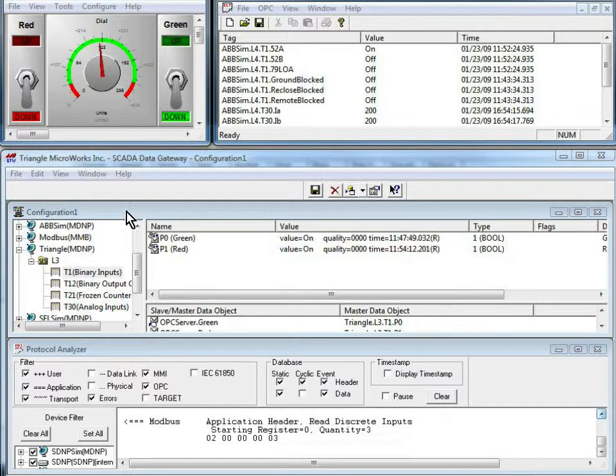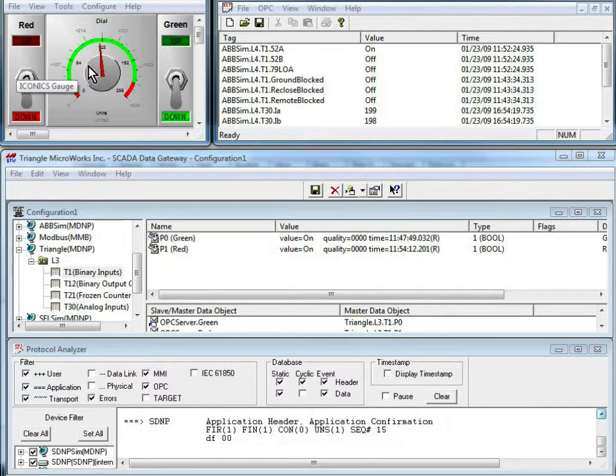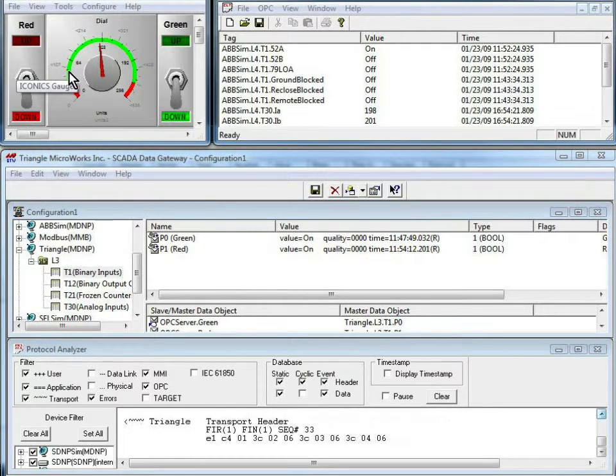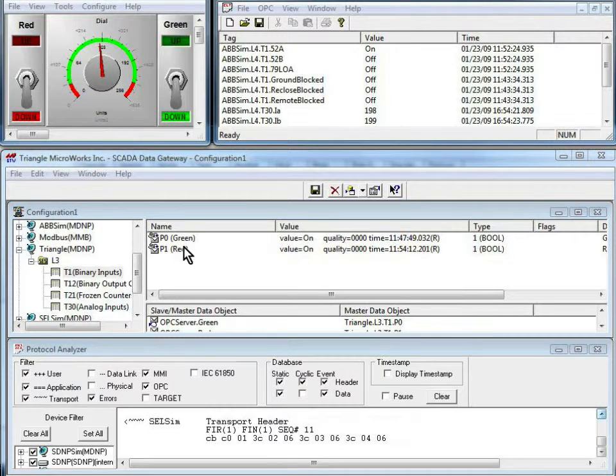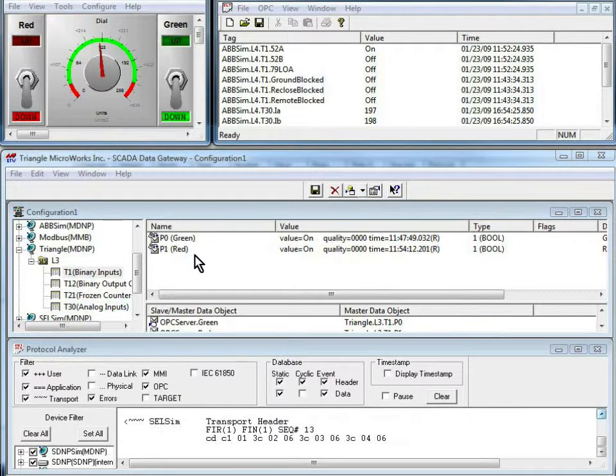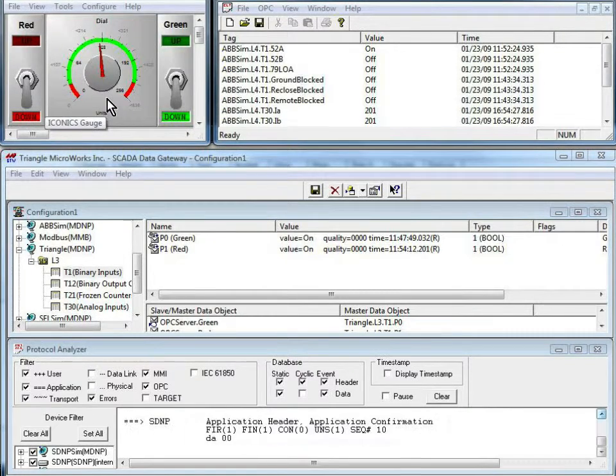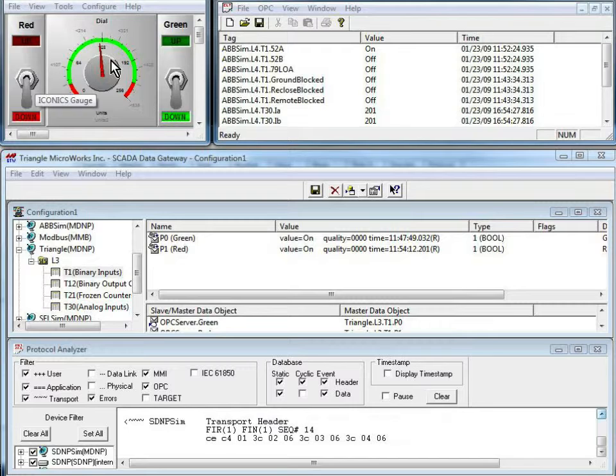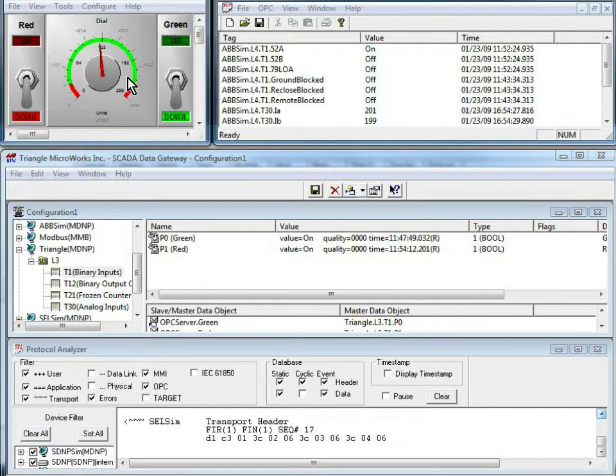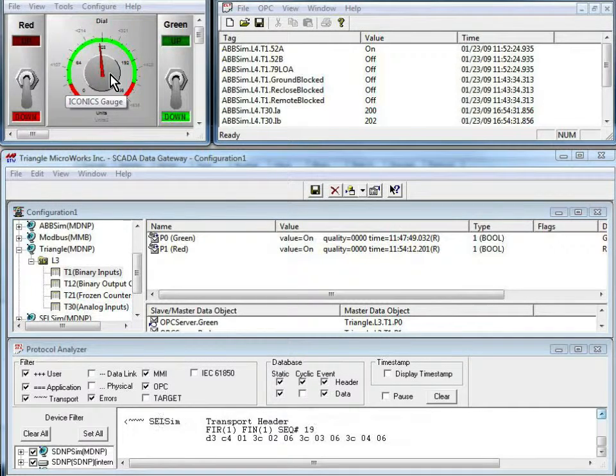So what happened here, we flipped the switch on the triangle, and that was reported up via DNP to the SCADA data gateway, and that was passed to an OPC client with a visual HMI to show the operator that the switch position changed.